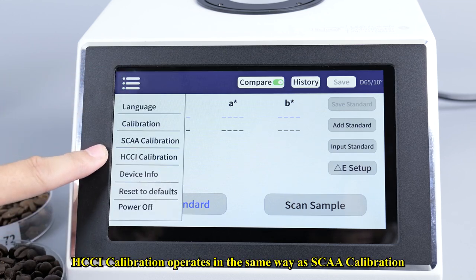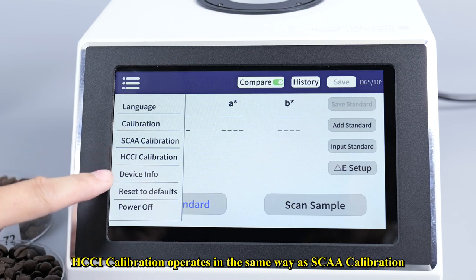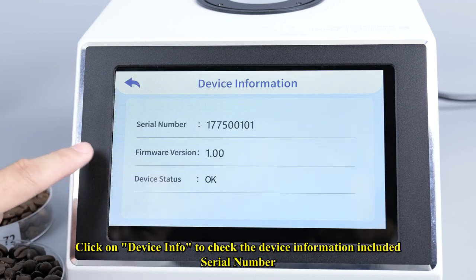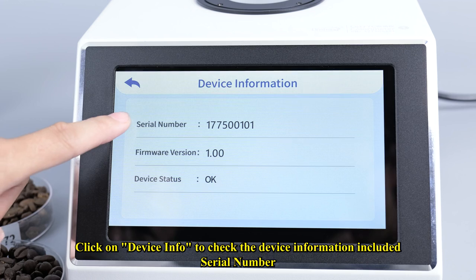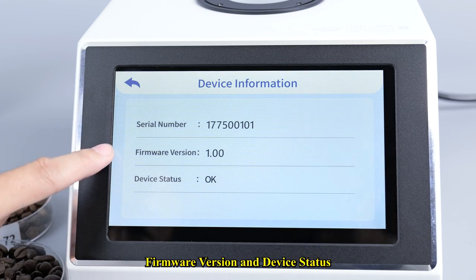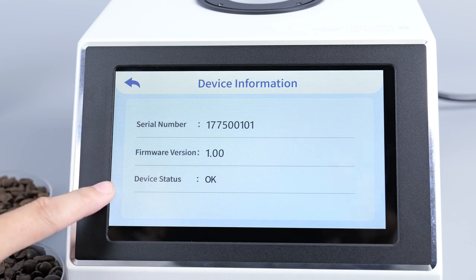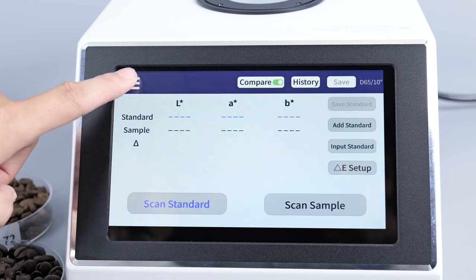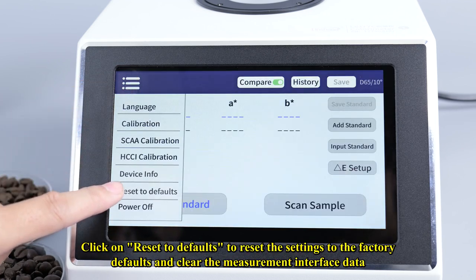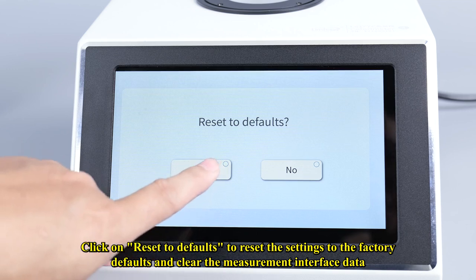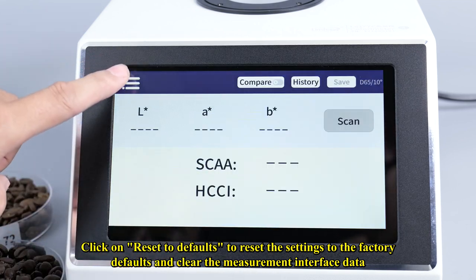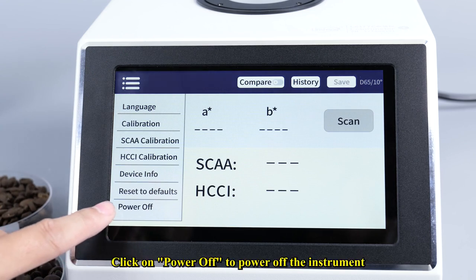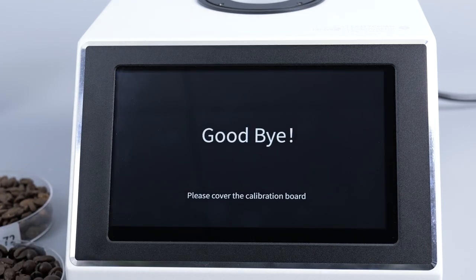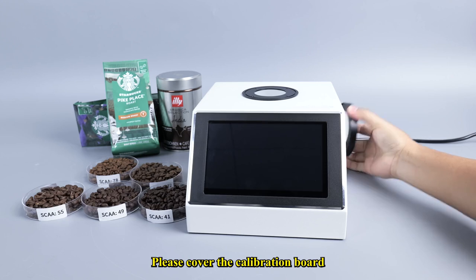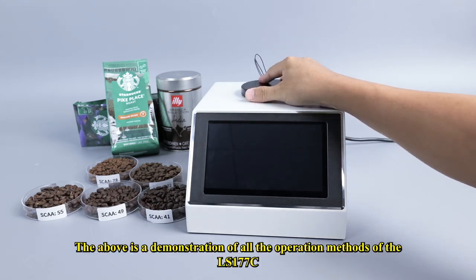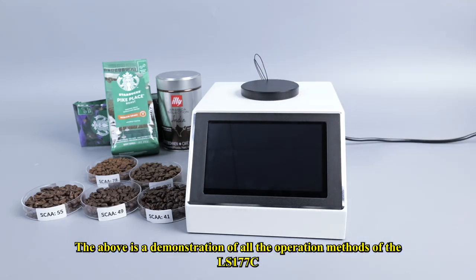HCCI calibration operates in the same way as SCAA calibration. Click on Device Info to check the device information, including serial number, firmware version and device status. Click on Reset to Defaults to reset the settings to the factory defaults and clear the measurement interface data. Click on Power Off to power off the instrument. Please cover the calibration board. The above is a demonstration of all the operation methods of the LS177C.